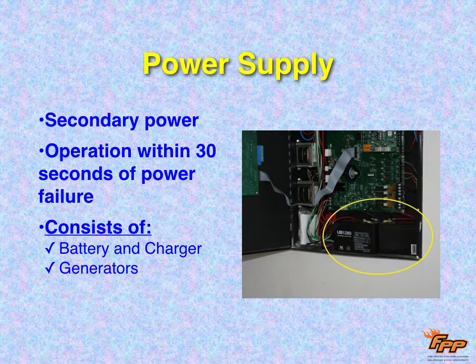Every alarm system needs a primary power, which is going to come from the electrical. And it'll be tied into the electrical panel like everything else in the building. But they're also required to have secondary power, which is usually going to be batteries, but in larger buildings, it might be generators.